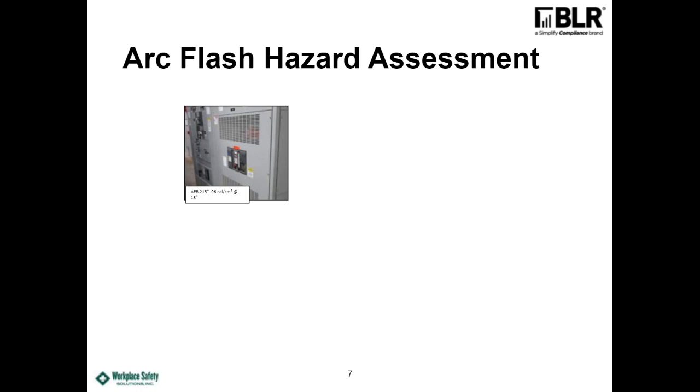The arc flash boundary was 215 inches, and the calorie rating was 96 calories per square centimeter. So that was an extremely high level arc flash. The arc flash level is going to be huge on that, mainly because it's an older transformer with a low impedance, and it's very big. So there's a lot of available fault current from that.